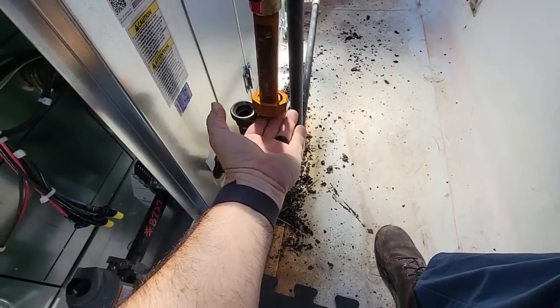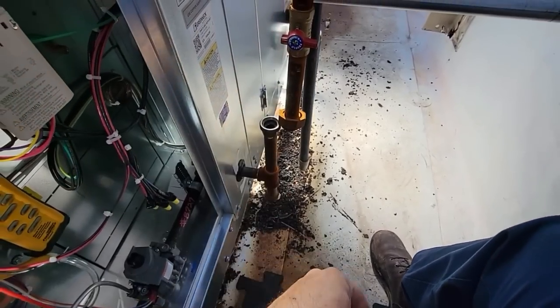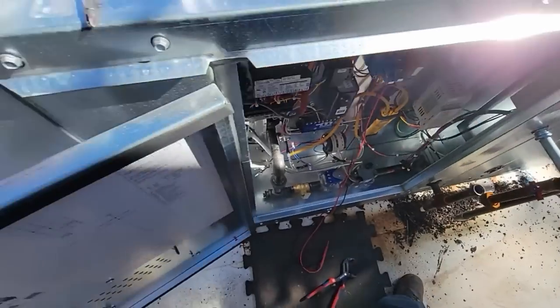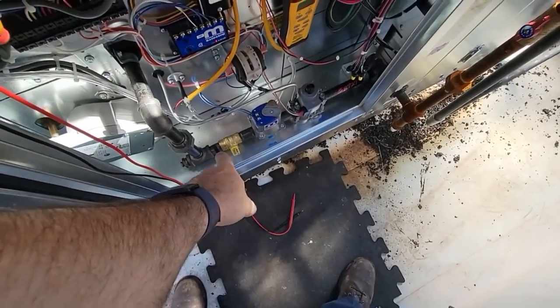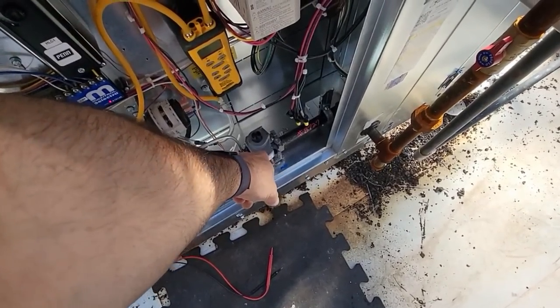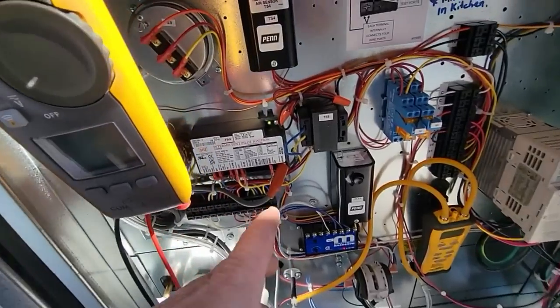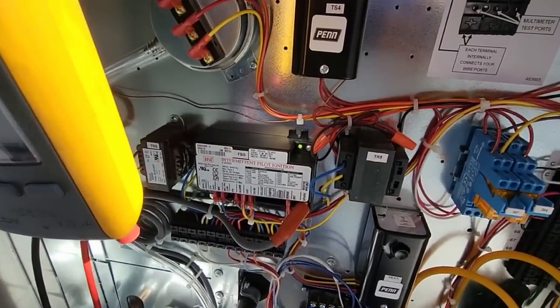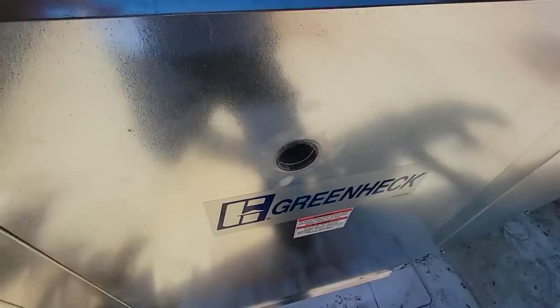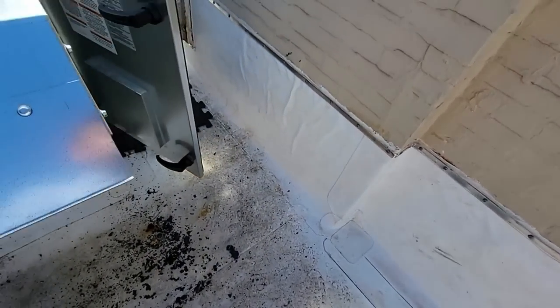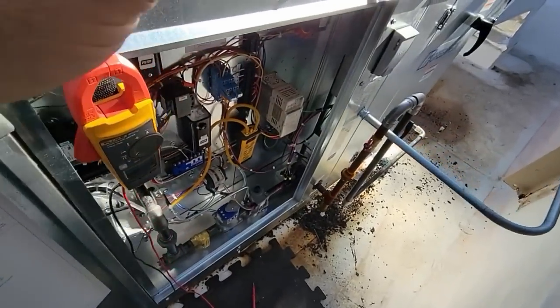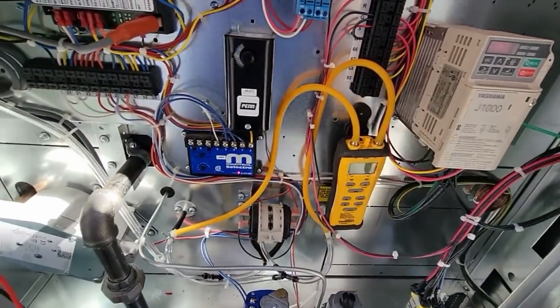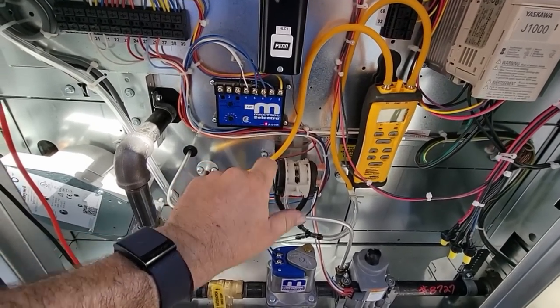All right. We're bled out good now. Let's try this again. We've got the main shut off going to the main burner, but that still allows the pilot valve to light. It did light. We have a solid green light there. So we should be able to see a pilot flame here. I can't even see it when I cut my eye over it, but it obviously must have lit because it's got a solid green. We turn on that main and see we got power to our Maxitrol valve there.